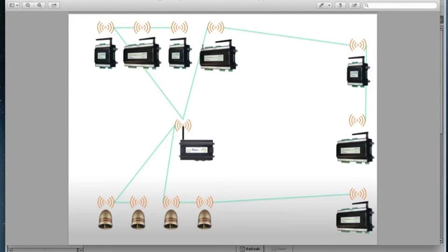So in this case, if communication loss takes place or power failure on one of the devices, the network simply switches and finds another route. So as you can see from the previous screen, we had 4 children, we lost 1, so the child at the top middle is now communicating to the majority of the page, and now the other 2 devices have maintained their connection. And then as networks change, again, now we have 5 children and the device is maintaining communication on the network. So very strong network. They function very well in maintaining the self-healing portion of the network.